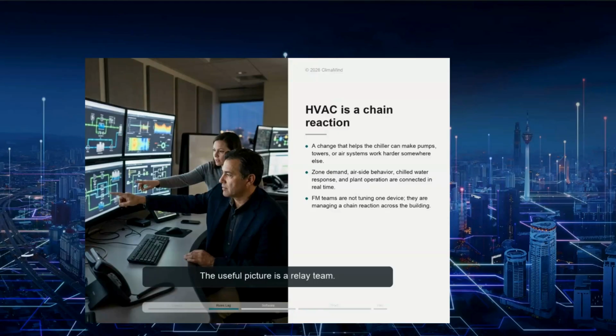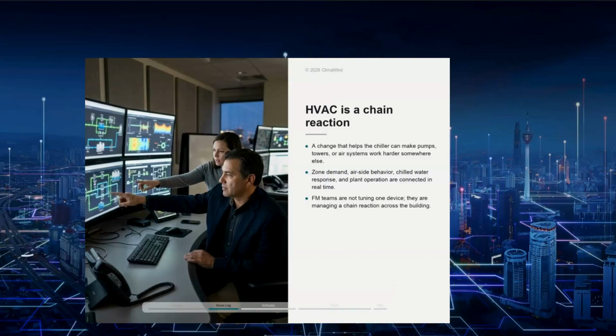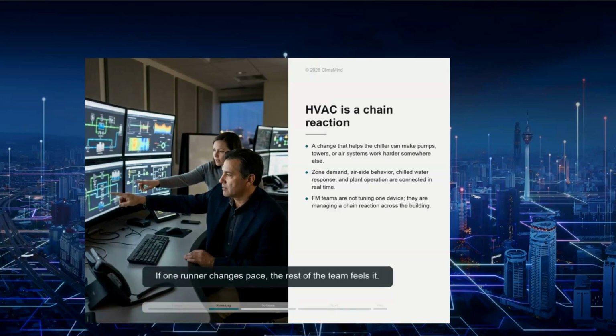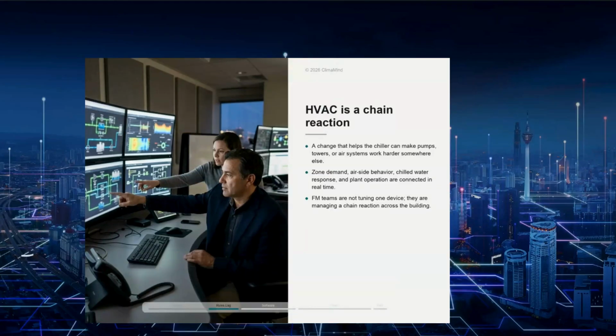The useful picture is a relay team. The room gives heat to the air system. The air system passes that demand to chilled water. Chilled water brings it to the plant. The plant pushes it outside. If one runner changes pace, the rest of the team feels it. That is why manual optimization is hard. The facility team is not tuning one device. They are managing a chain reaction.